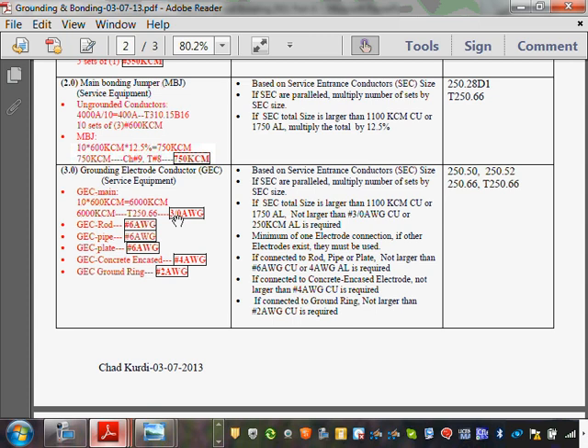That does not need to go larger than number 6. If it's solely going to the rod, just one rod, it does not need to be more than number 6. The one that's going to the pipe, not more than number 6. These are all from the code. If it's going to a plate, it does not have to be larger than number 6. Concrete encased electrodes, not larger than number 4. A grounding ring, number 2.